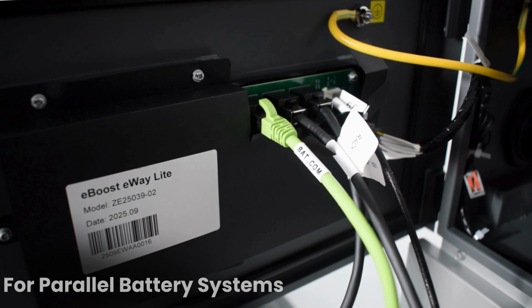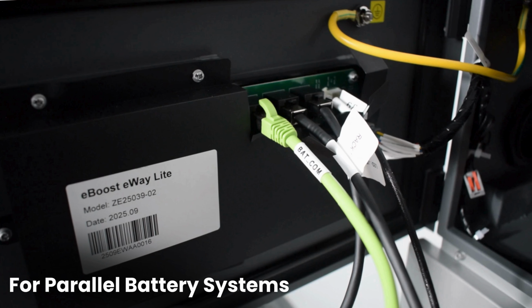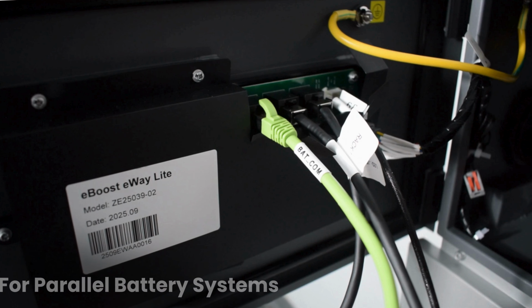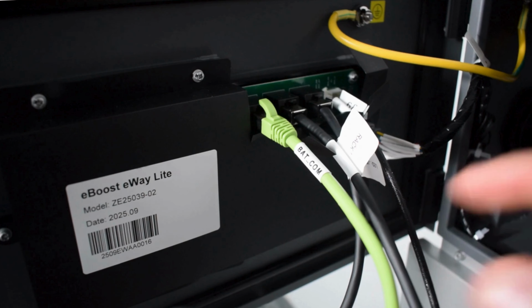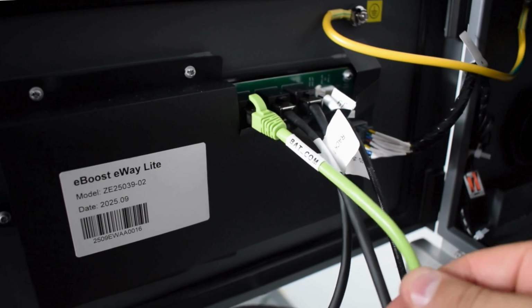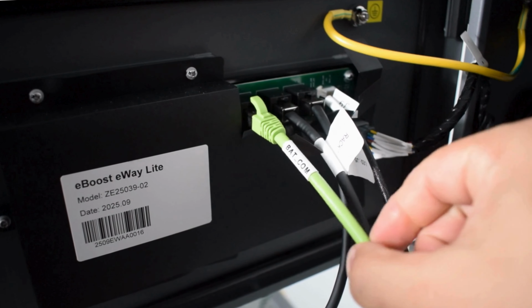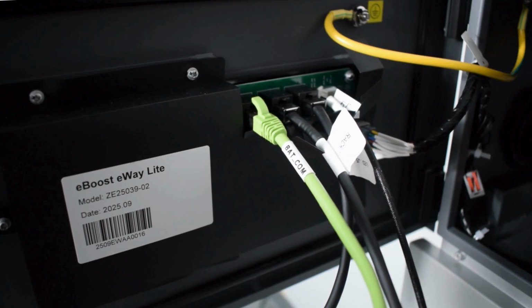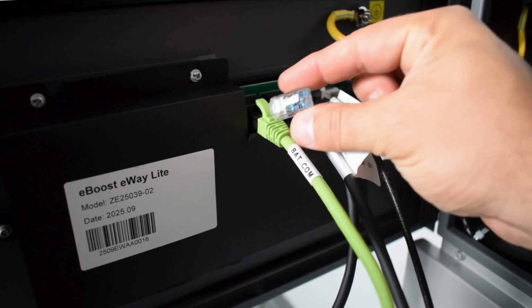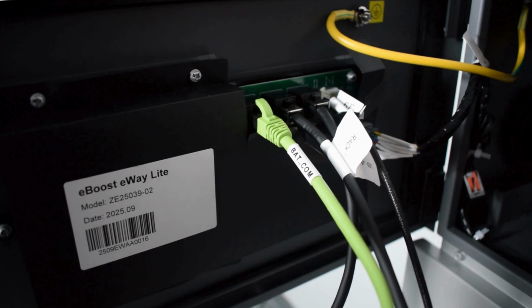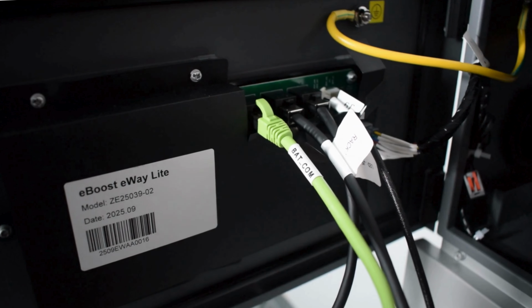In a parallel battery system, meaning there are multiple batteries, you connect the Guardian at the primary battery. You can identify the primary battery because the last battery in the chain will have a terminator connected. Since this is the primary battery, it won't have the terminator plugged in; instead it will have the communication cable that goes from battery to battery, and the power relay cable that also goes from battery to battery.